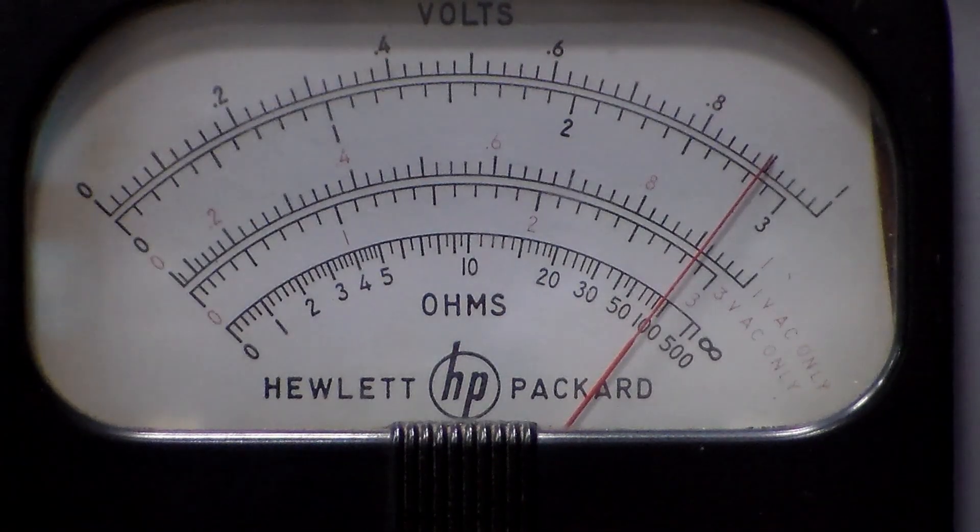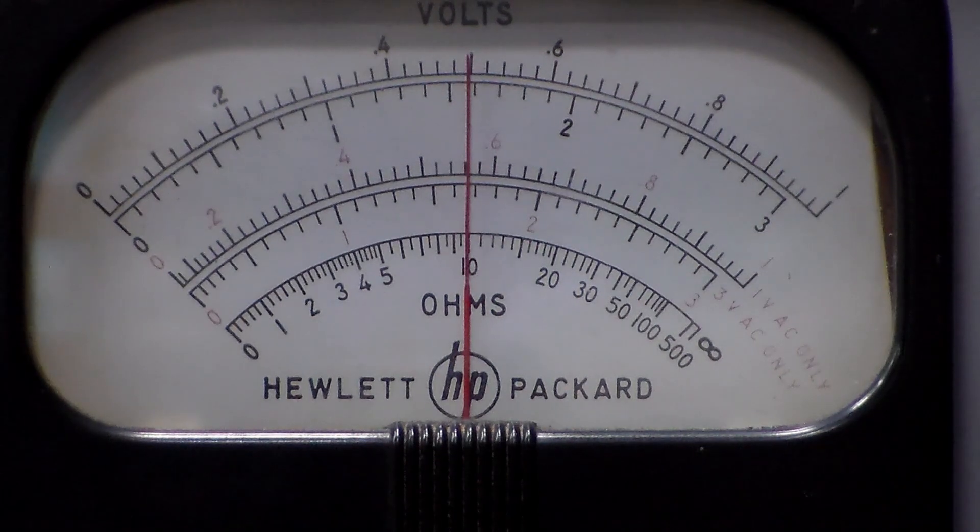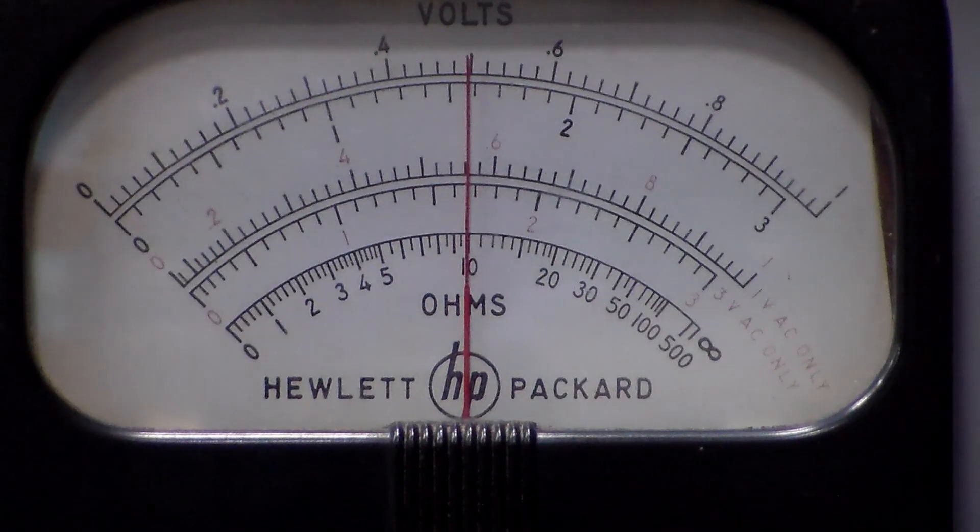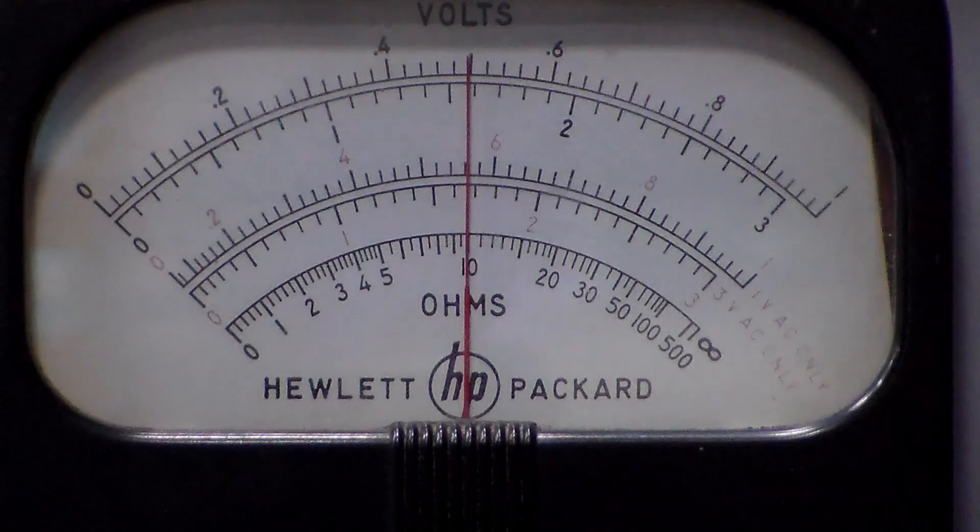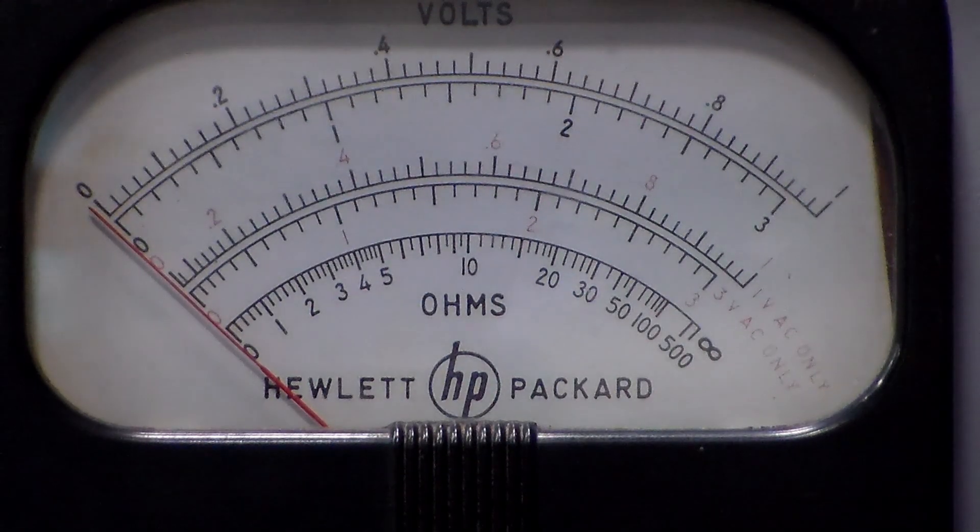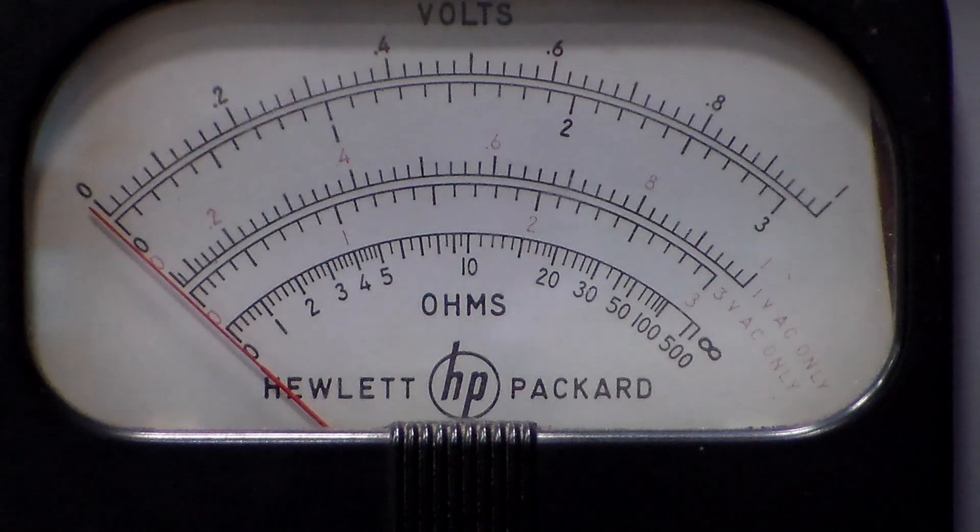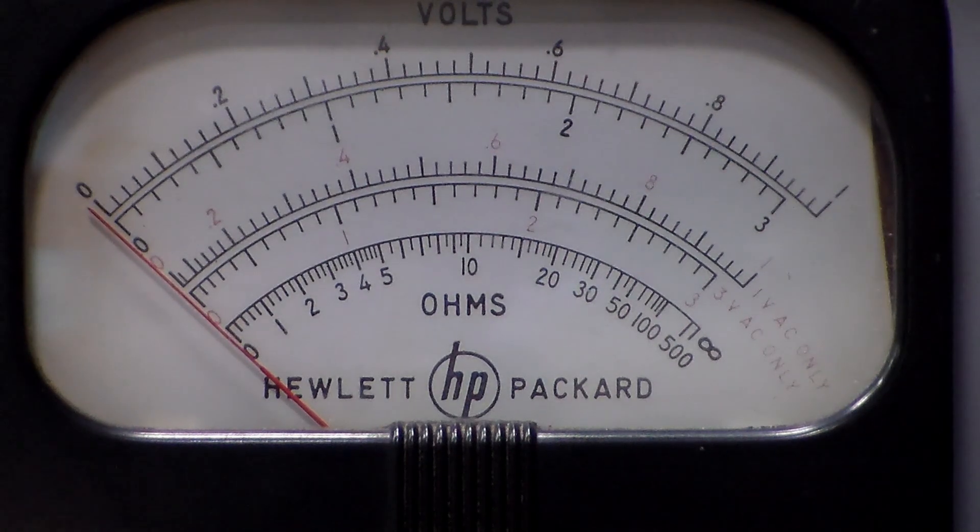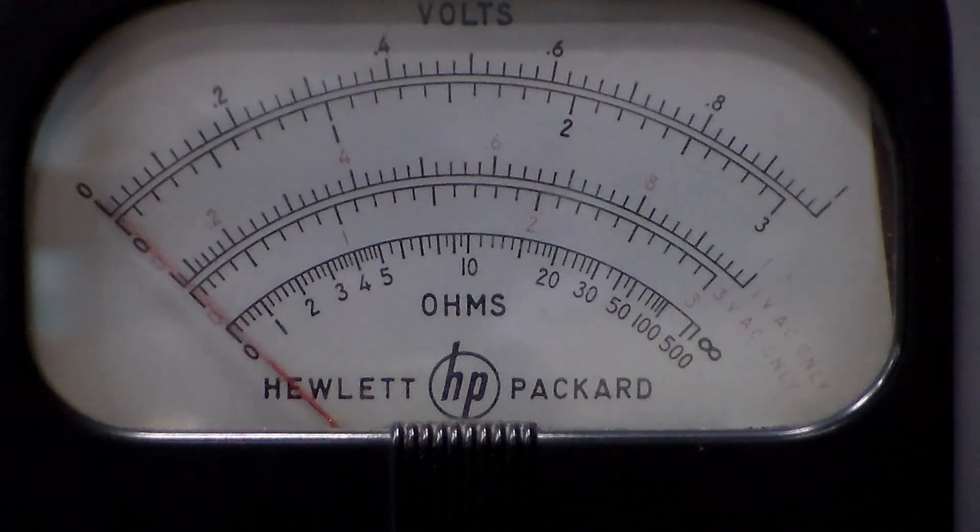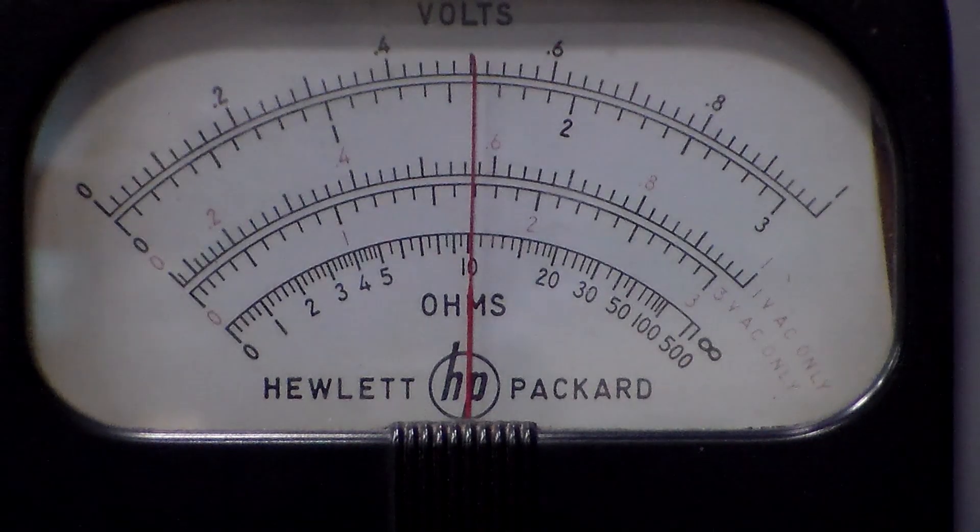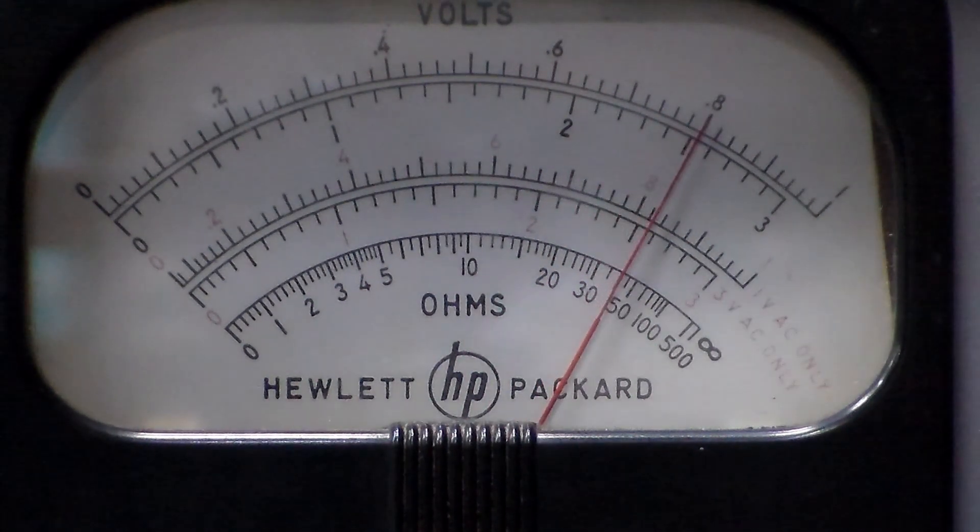We'll go now onto the times 10 range. We'll show 10 on there and we're reading pretty well spot on there. I'll just run this back to zero. We are actually on this range showing slightly our zero position is slightly out, so we'll just re-zero that so we can check. There's 100, 200, 300, 400, 500 and so on.